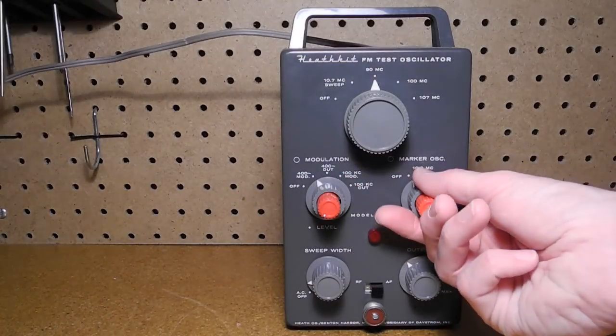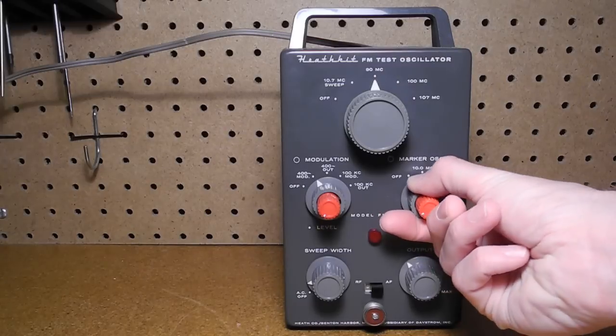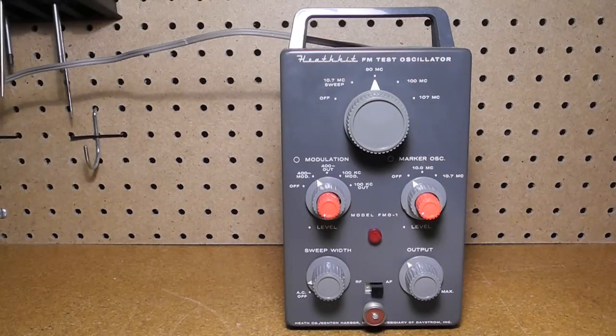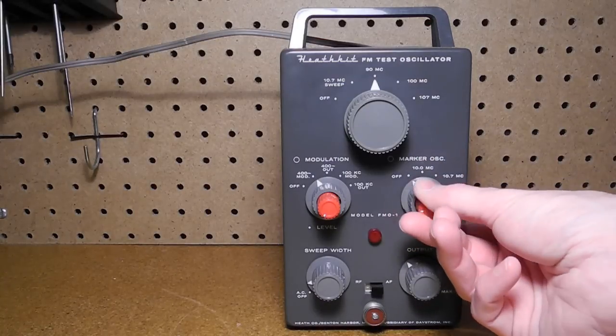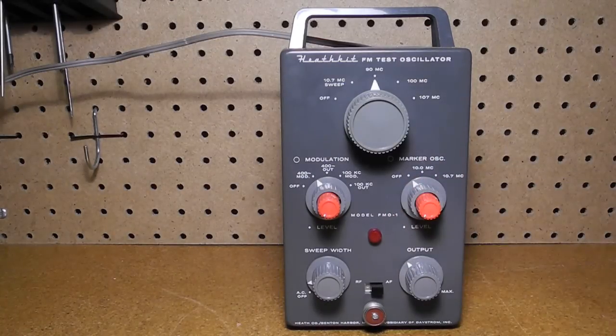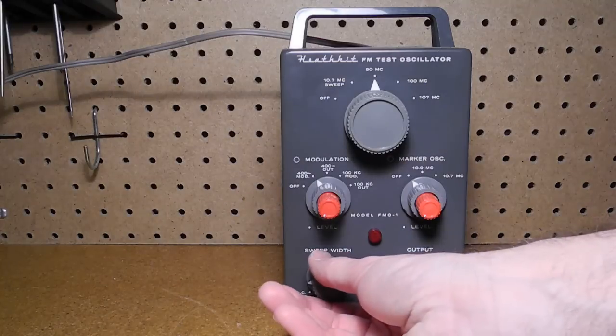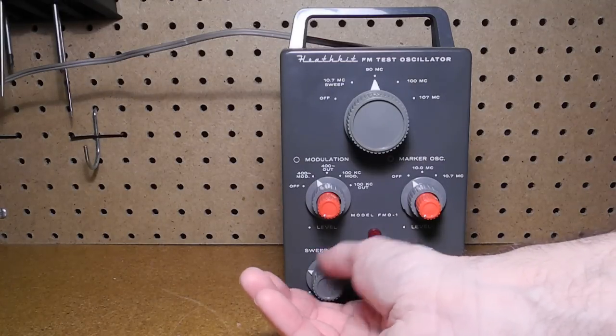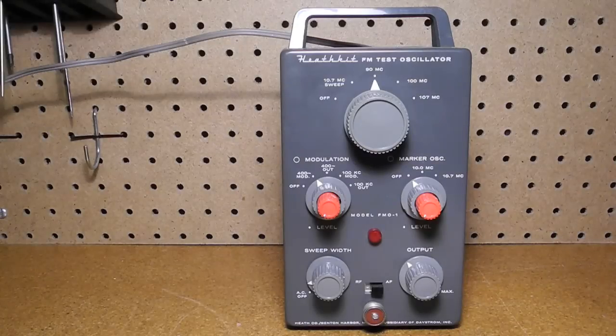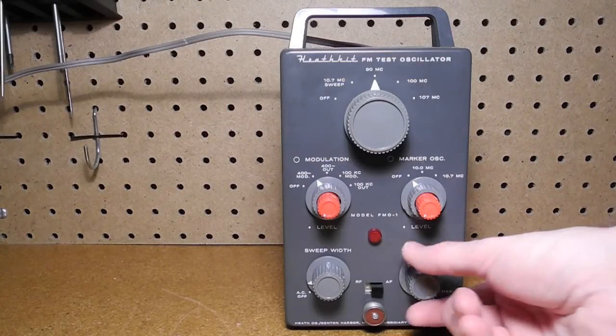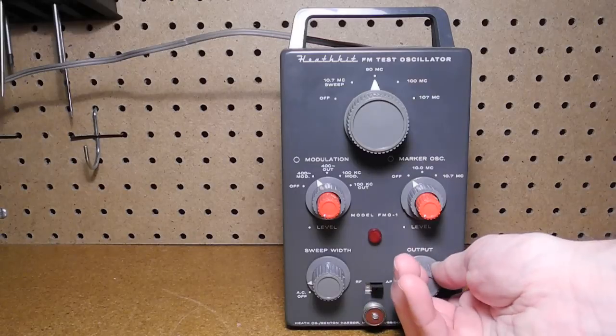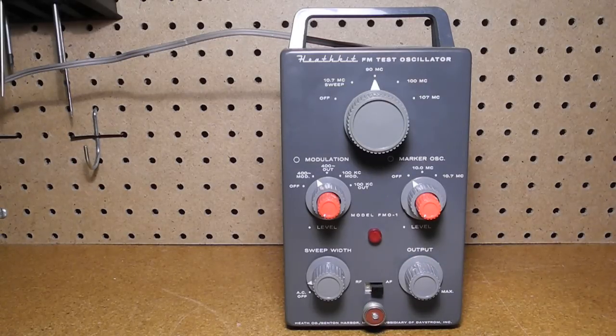The marker oscillator knob selects an additional marker generator signal and can be one of marker off, a 10 MHz marker, or a 10.7 MHz marker. The red inner knob controls the level of the marker generator signal. The sweep width control adjusts the width of the 10.7 MHz sweep signal. The sweep frequency is always 60 Hz, but the width can vary from about 200 kHz to 1 MHz. The output control adjusts the level of the combined signal at the output jack.